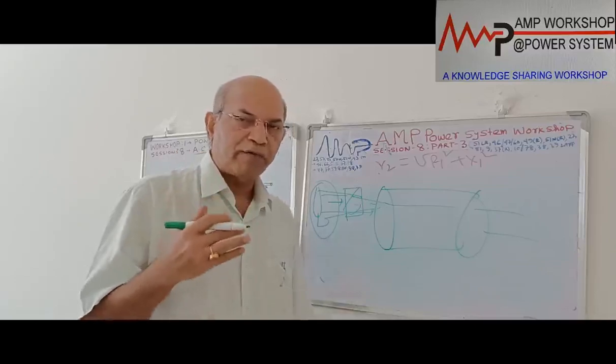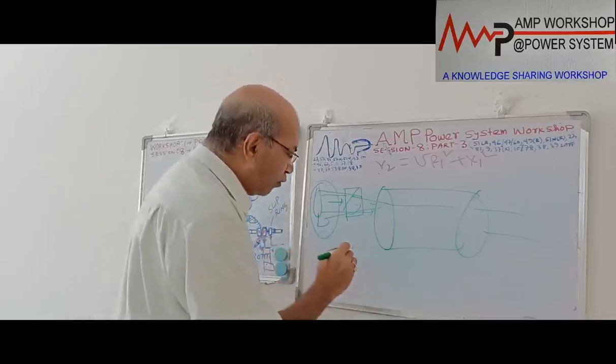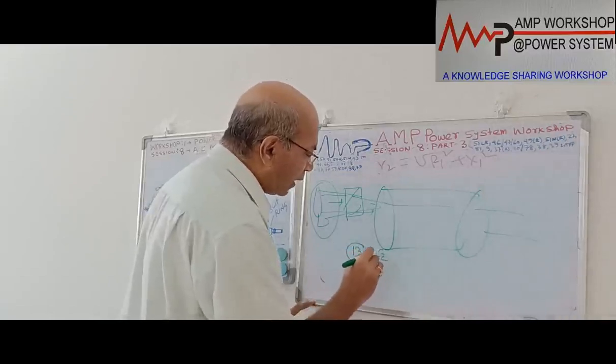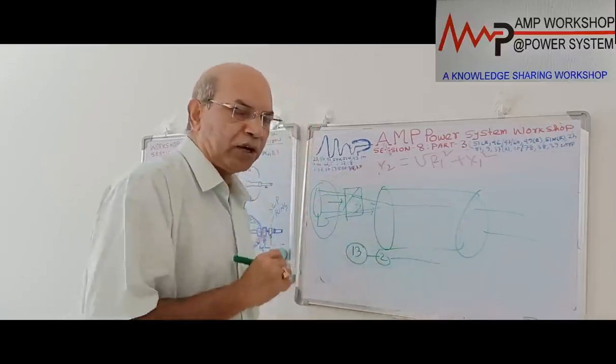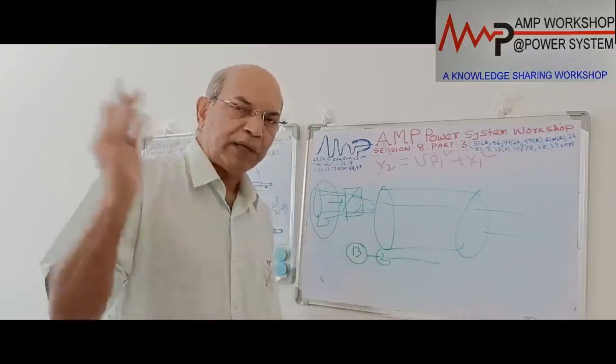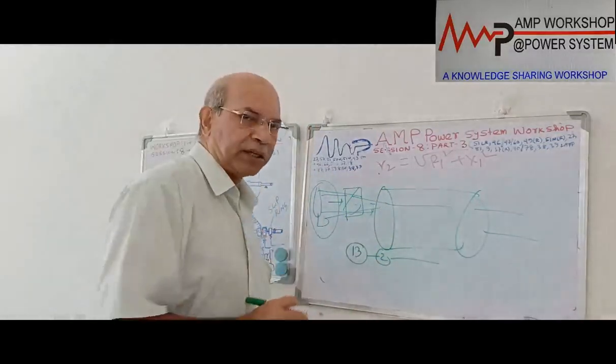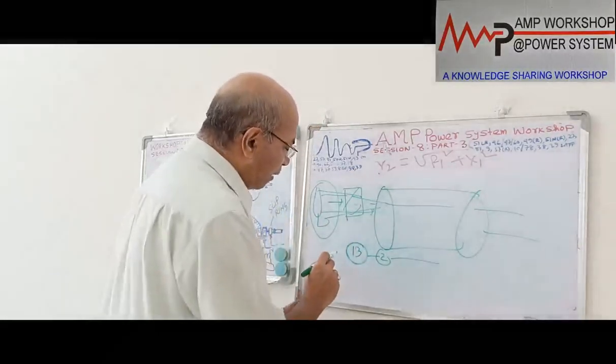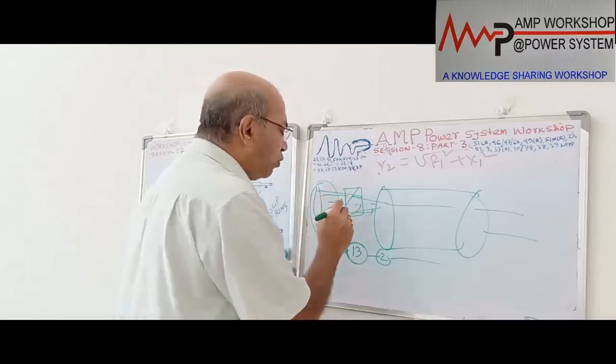If the adequate amount of flow is not there, then the flow switch contact with a timer will give the alarm. It will not give the trip; if it is an attended motor, then it will give an alarm, and the control room operator will come and see the condition. So either it gives the alarm by flow switch, or you can do it another way.